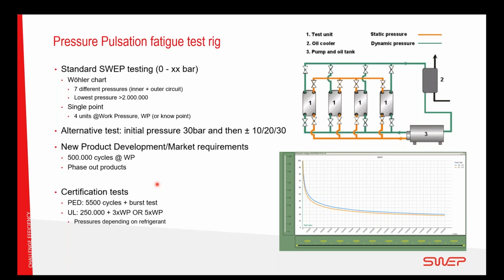Or, for example, the UL testing, where you run a much higher number of cycles and then end it with pressurizing to 3 times the work pressure, or you do a test with 5 times the work pressure before burst. And these pressures also depend on which refrigerant you are using for the heat exchanger and what approvals are needed.